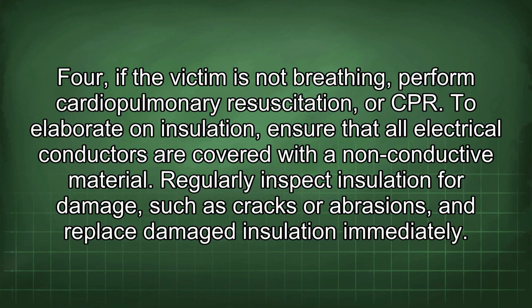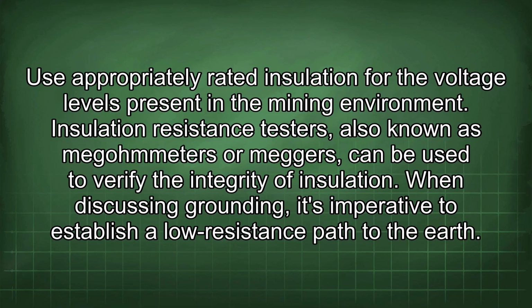To elaborate on insulation, ensure that all electrical conductors are covered with a non-conductive material. Regularly inspect insulation for damage, such as cracks or abrasions, and replace damaged insulation immediately. Use appropriately rated insulation for the voltage levels present in the mining environment. Insulation resistance testers, also known as megohmmeters or meggers, can be used to verify the integrity of insulation.